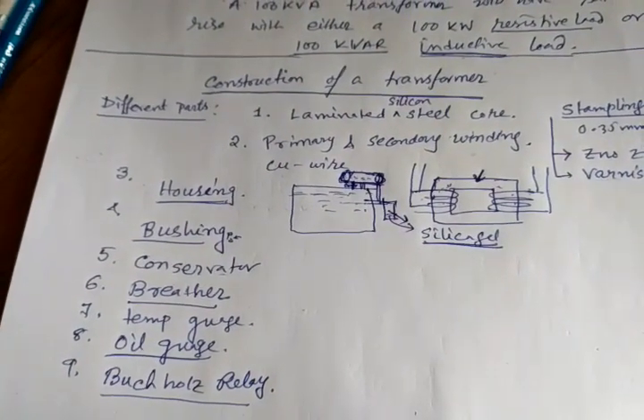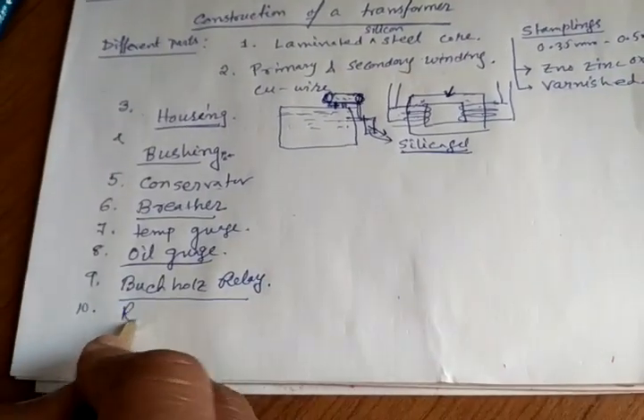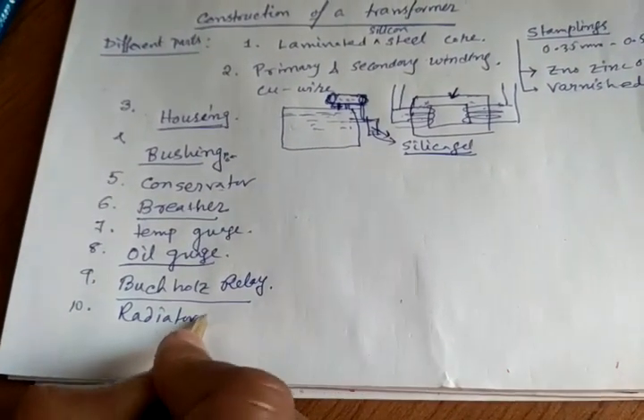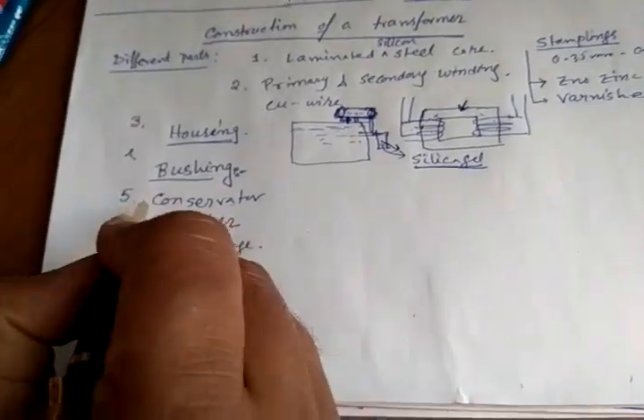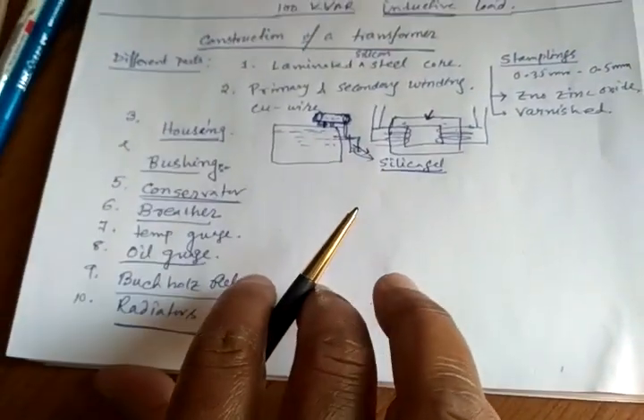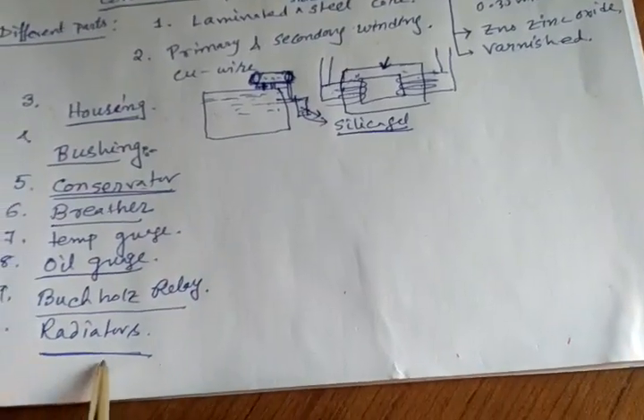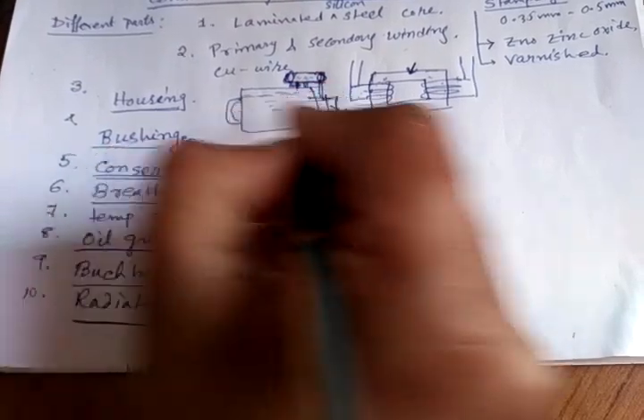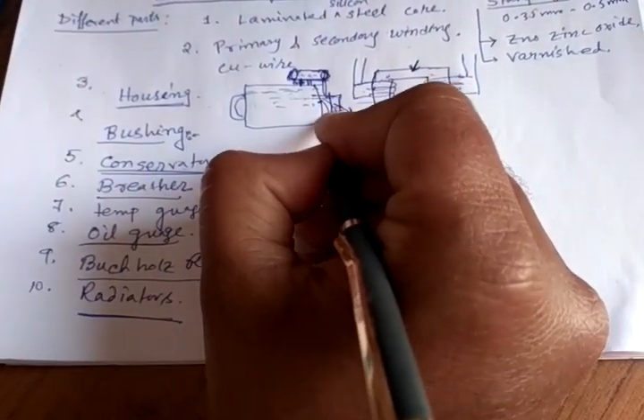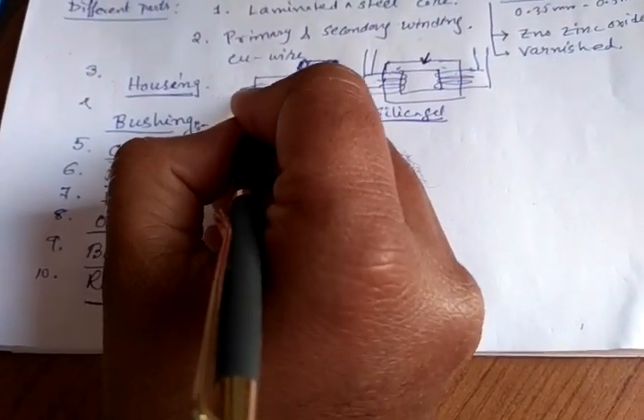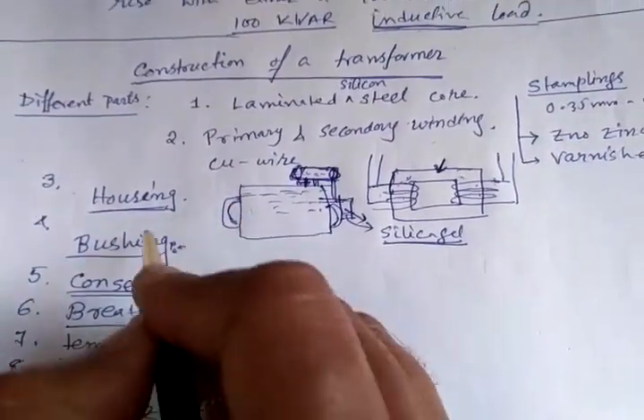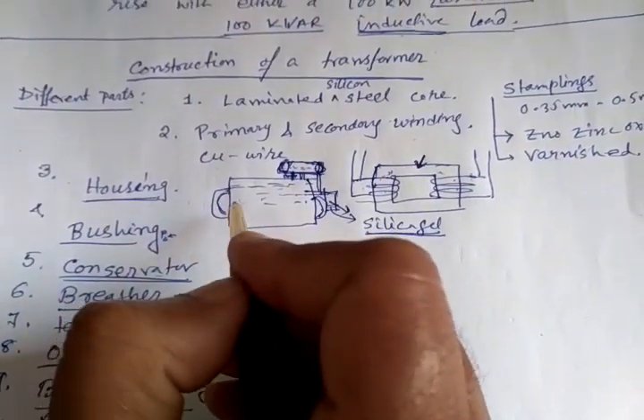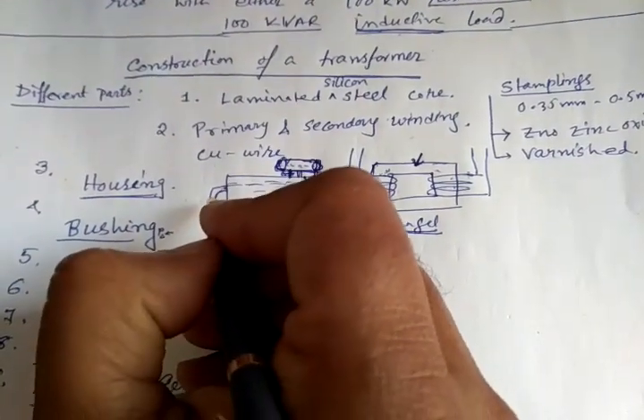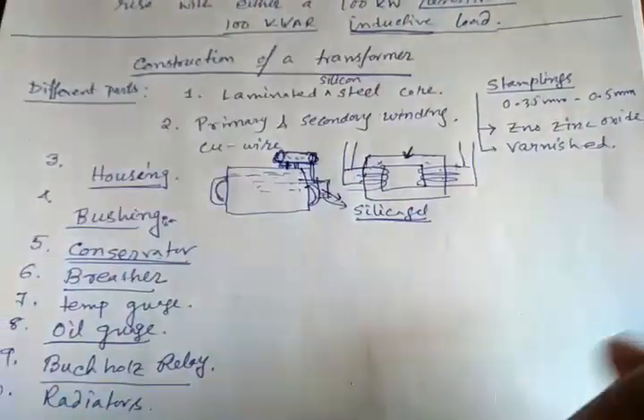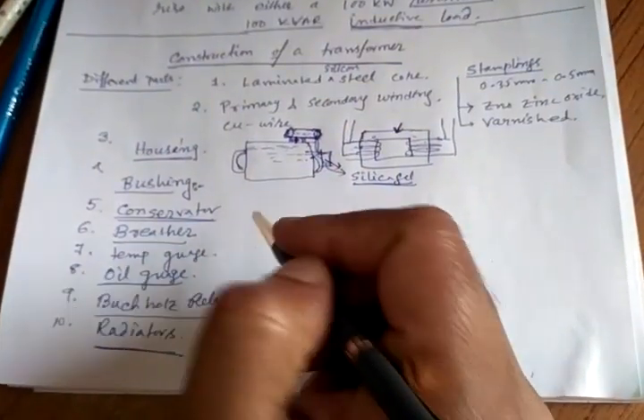Other than that, one more important thing is radiators. This radiator part and conservator part we also discuss while we discuss the cooling of transformer. Basically radiators are outside the tank. This is basically used to cool the transformer oil, to dissipate the heat generated in the windings. So these are known as radiators. Okay, this is basically in a simple way the construction of a large transformer.